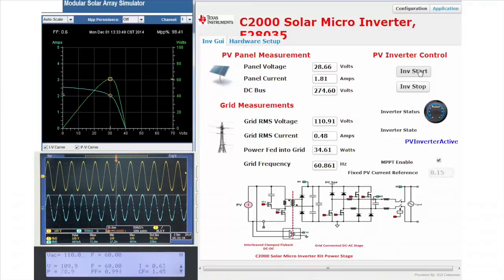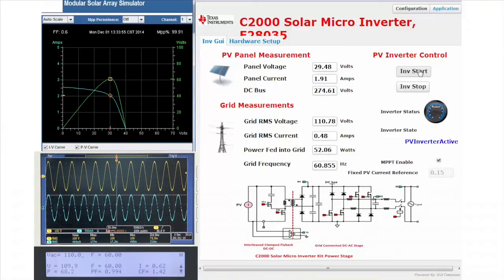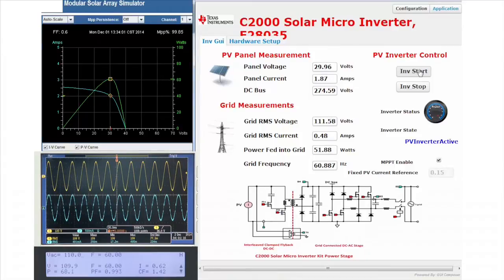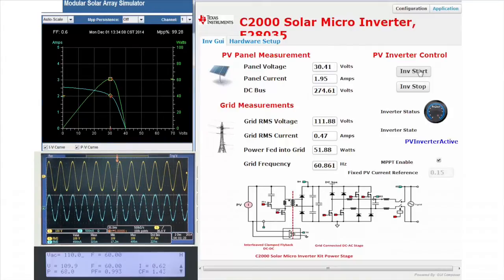We see as the inverter starts, the power sourced from the AC source for the local load will drop and the PV inverter current will increase. MPPT tracking performance can be seen from the GUI associated with the panel emulator and is seen to be close to 99 to 100 percent.